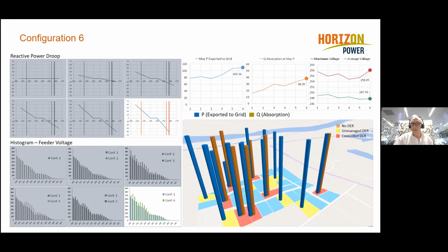Now this slide shows one of those unmanaged PV systems that was part of that test. Prior to reactive power control, the inverter in question was unable to operate effectively because of high volts on the feeder. During the reactive power control experiments that were performed, there was a marked improvement in the performance of the inverter because the voltage on that part of the feeder was improved.